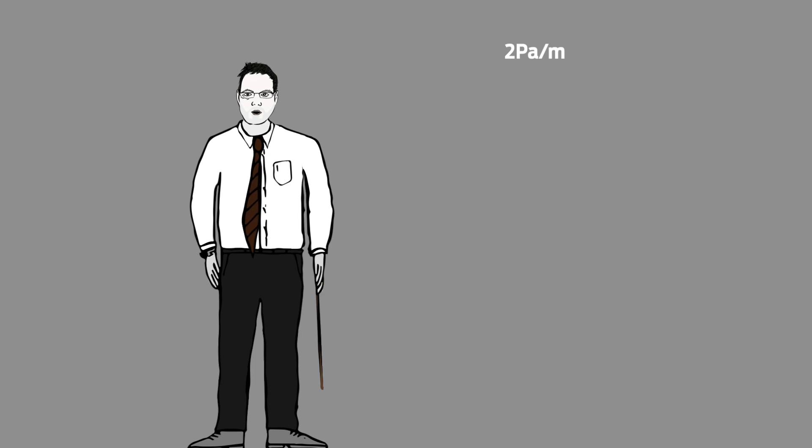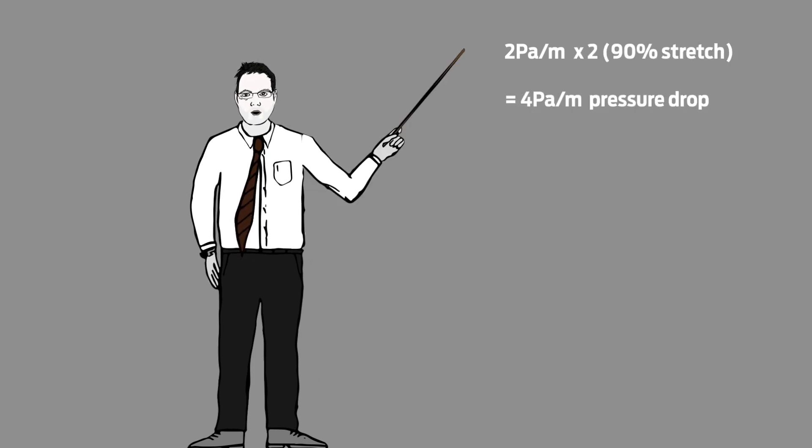If we now multiply the ducting pressure drop by 2, this will give us 4 Pa per metre, which is well above the 2.45 we just worked out. In this case, it won't work to the flow required, so what are your options?